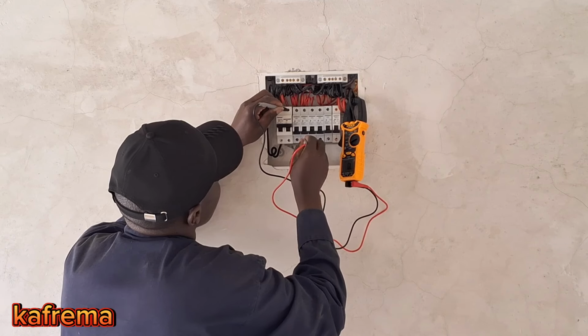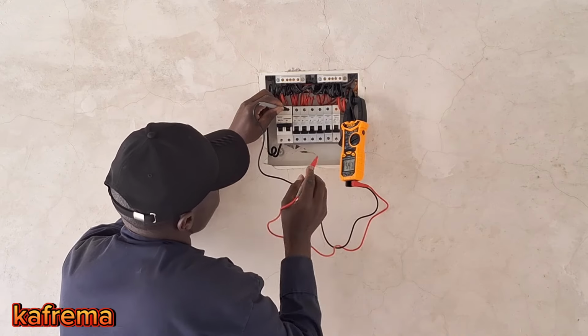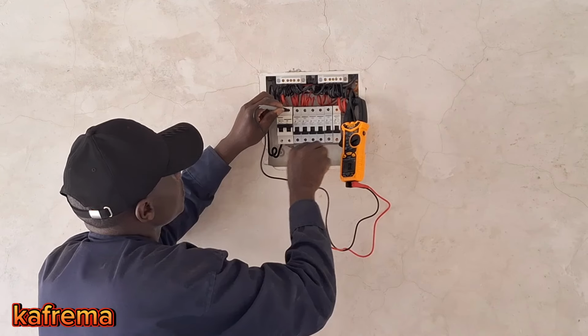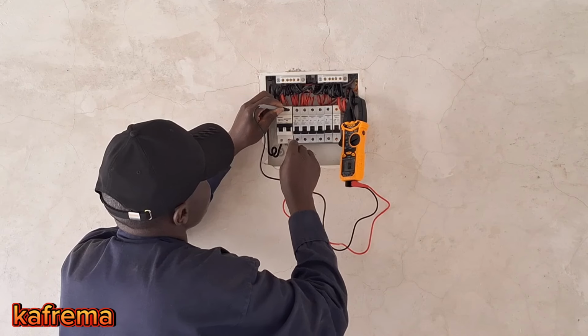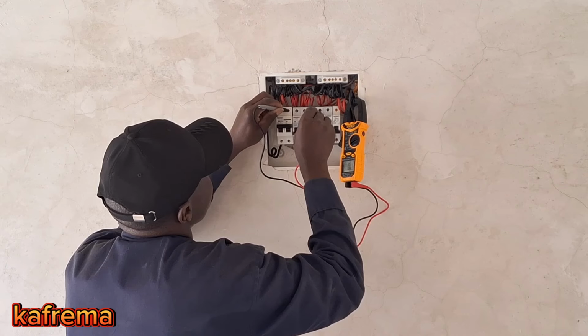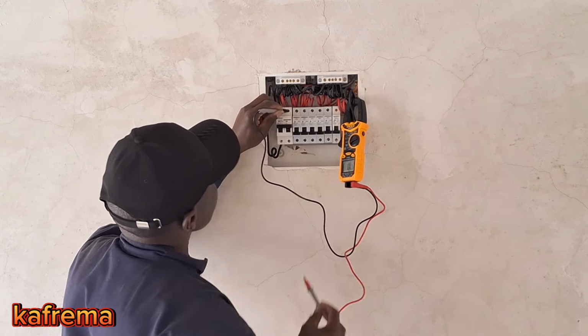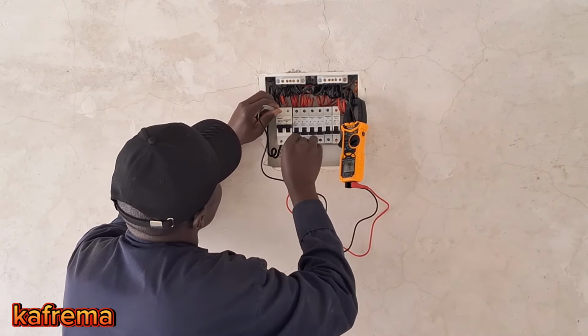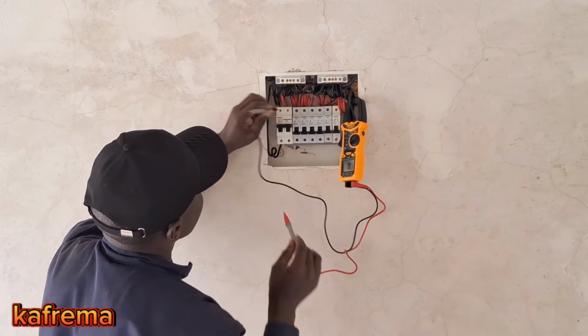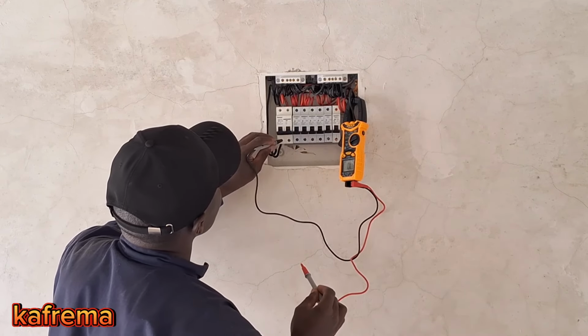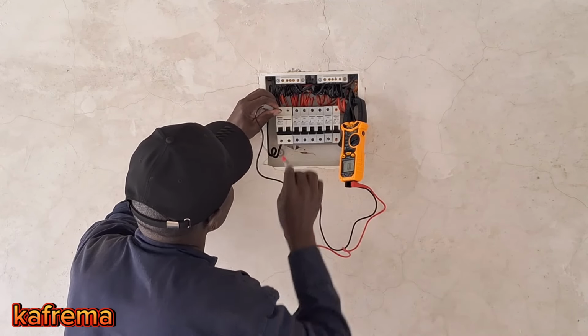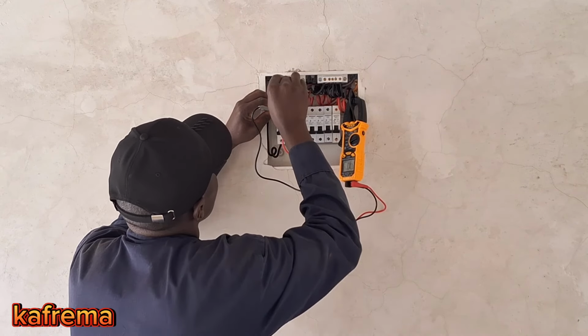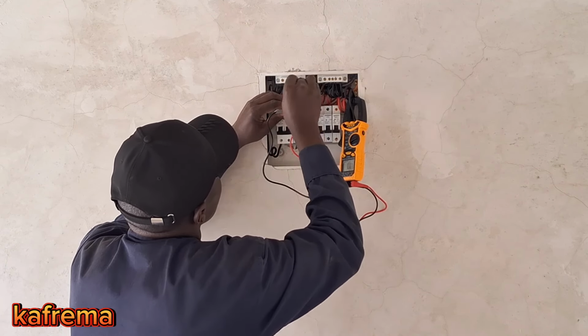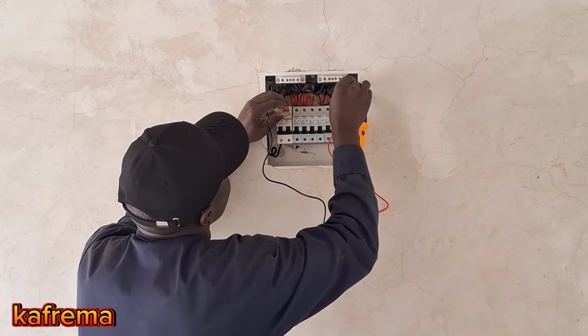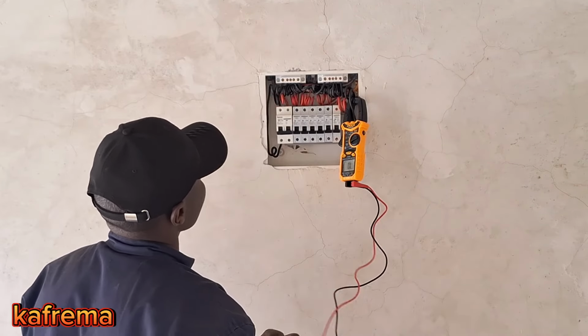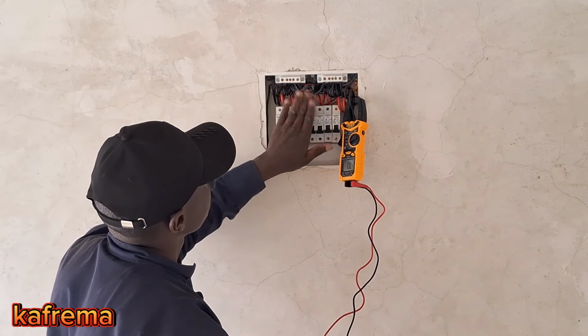You know, it should be continuous here. When we switch off, the lower side will be powered because all these points are connected, but on the upper side there should be no continuity. No continuity to the line side from the neutral side. When we switch it off, there should be no continuity from here to anywhere, even on the line side, anywhere, even to the earth. So our consumer unit is very okay.